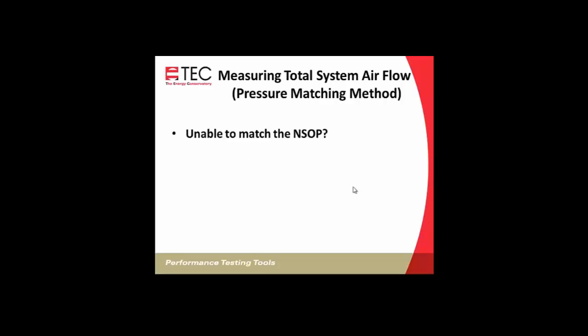If you're not able to match the normal system operating pressure, so maybe you've got a 5-ton system, because you're starting out before you start turning the Duct Blaster fan on, you've already got the air handler running and it's drawing air through the fan. You'll actually get a flow reading on your DG700 before you even turn up the speed controller. So it's got a negative back pressure on it. So it's pulling air through the fan, and in some cases, you may be able to get up to 2000 CFM through that fan. So you may be able to match the normal system operating pressure.